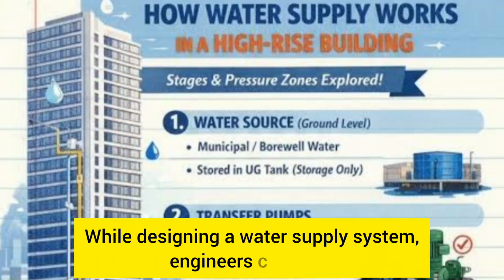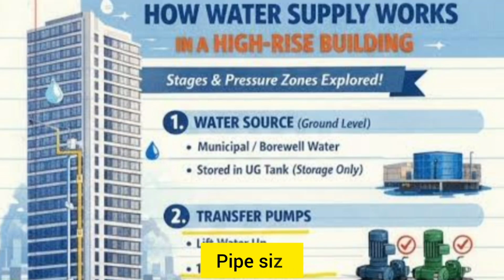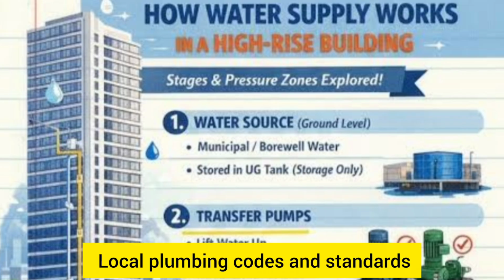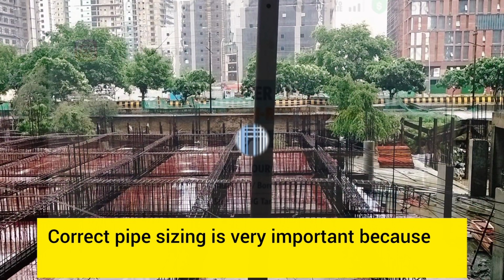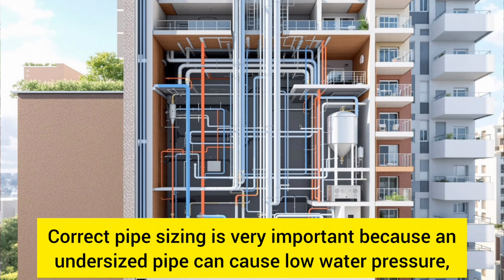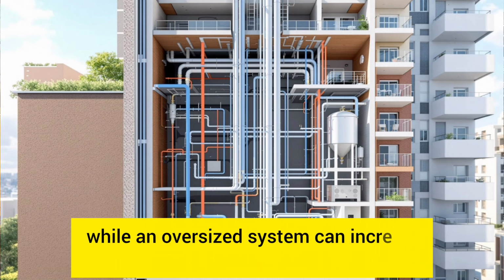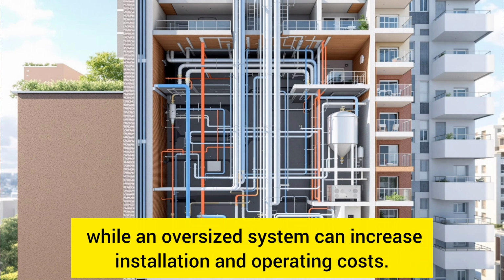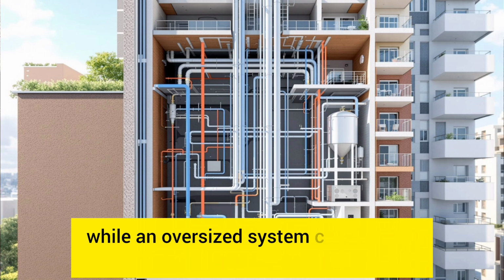Important design considerations. While designing a water supply system, engineers consider water demand, pipe size, flow rate, water pressure, building height, pipe material, pump capacity, storage capacity, fixture requirements, local plumbing codes and standards. Correct pipe sizing is very important because an undersized pipe can cause low water pressure, while an oversized system can increase installation and operating costs.